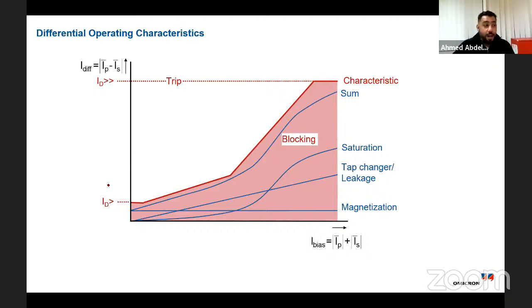After that, I need to draw a characteristic between the differential current and the restraint current. As you can see here, I draw a relationship between I differential, which is equal to the absolute value, as we said, of I primary minus I secondary, or you can say plus, as you wish. But when you say plus, you need to have this negative. So in general, it will be IP minus I secondary. And I bias, this is the very basic formula, equals the absolute value of I primary plus the absolute value of I secondary. And I plot both of them against each other to have a characteristic. We call it the differential operating characteristic. And you should keep in consideration that it's a scalar characteristic, not a vectorial characteristic.